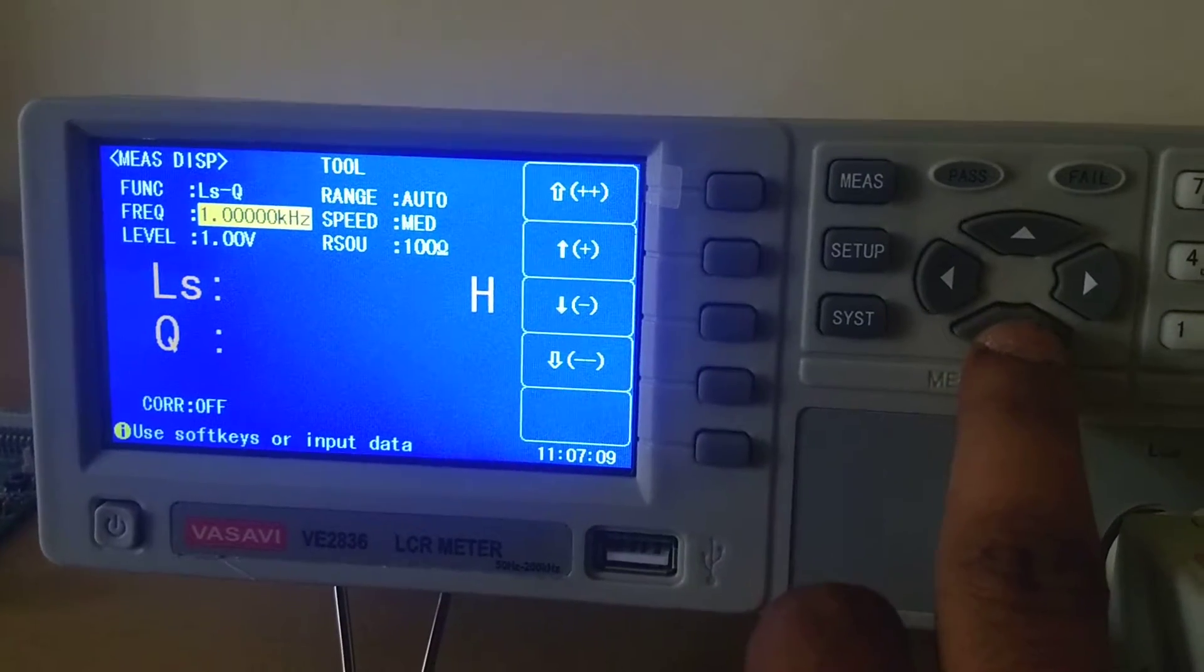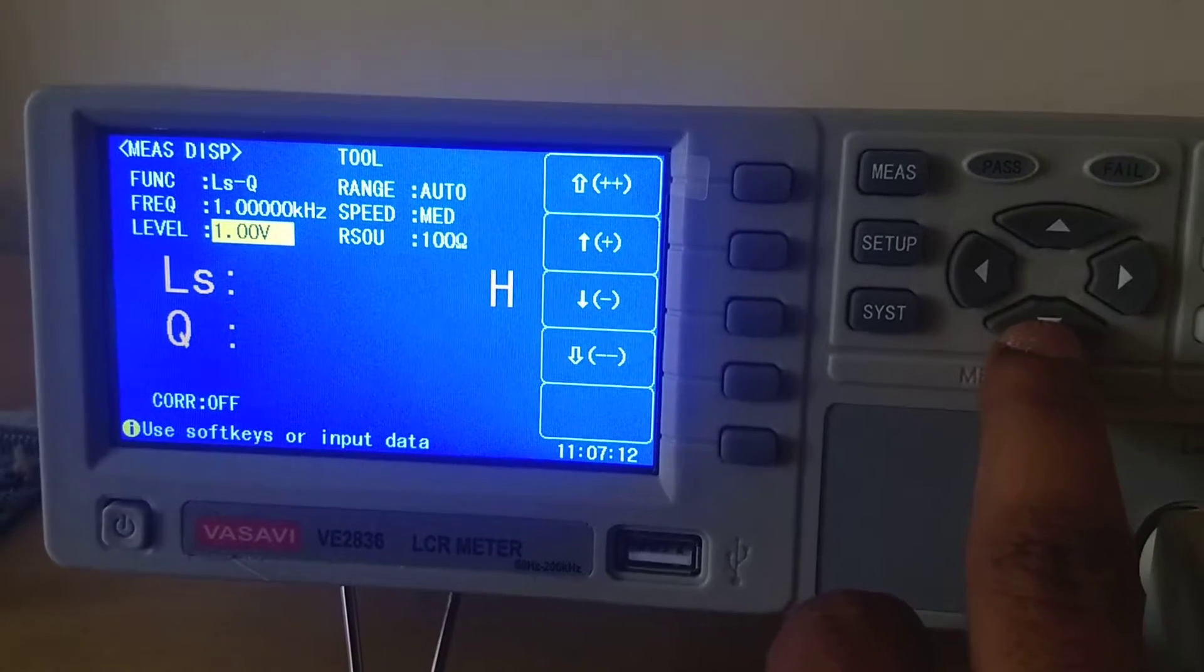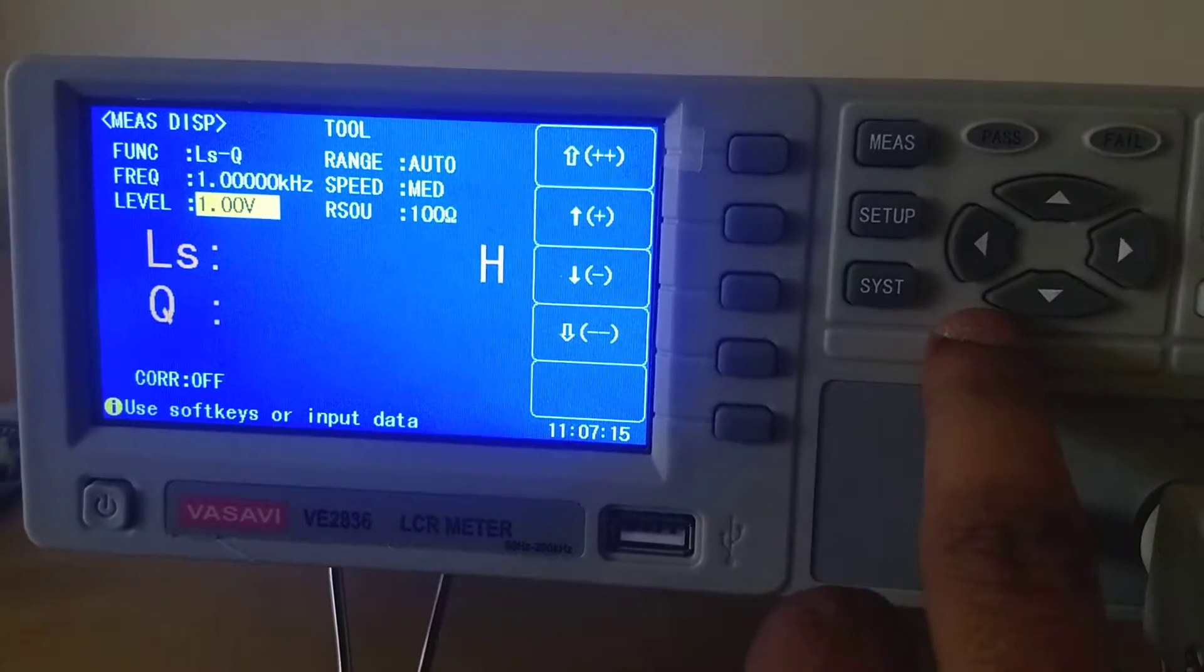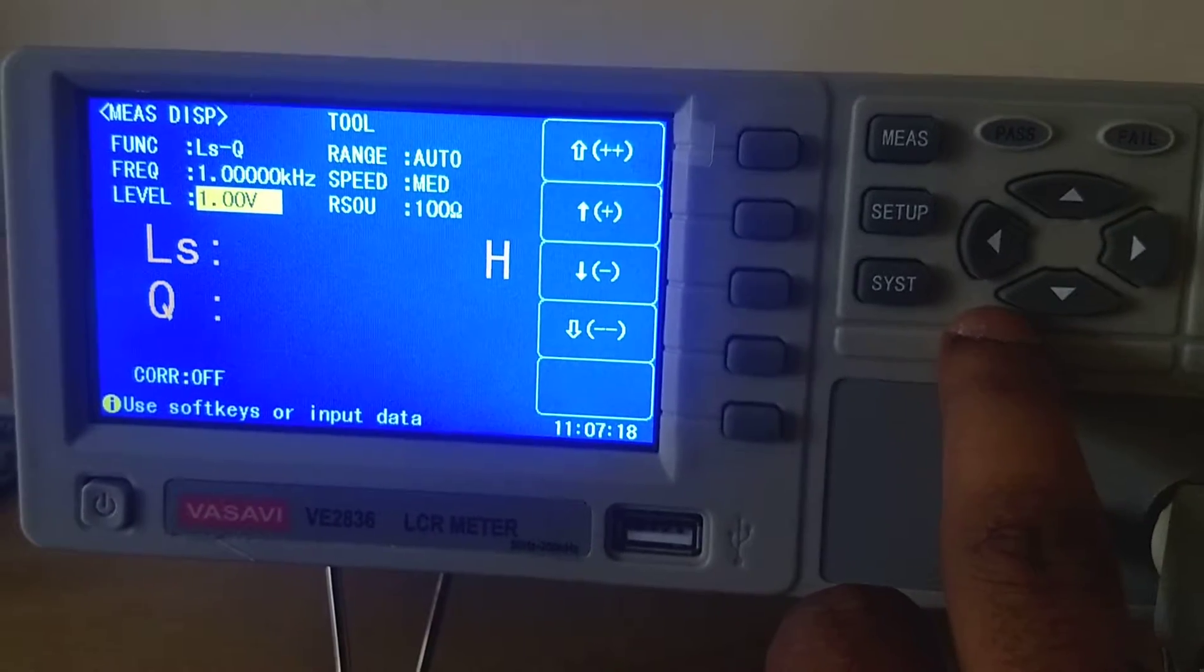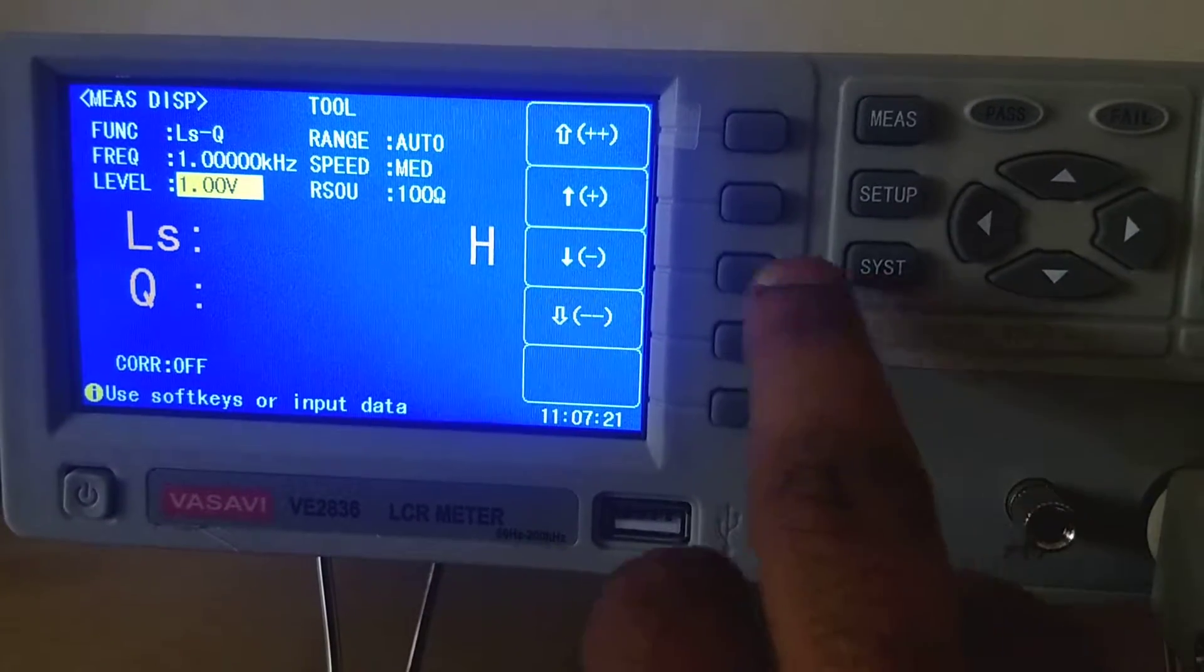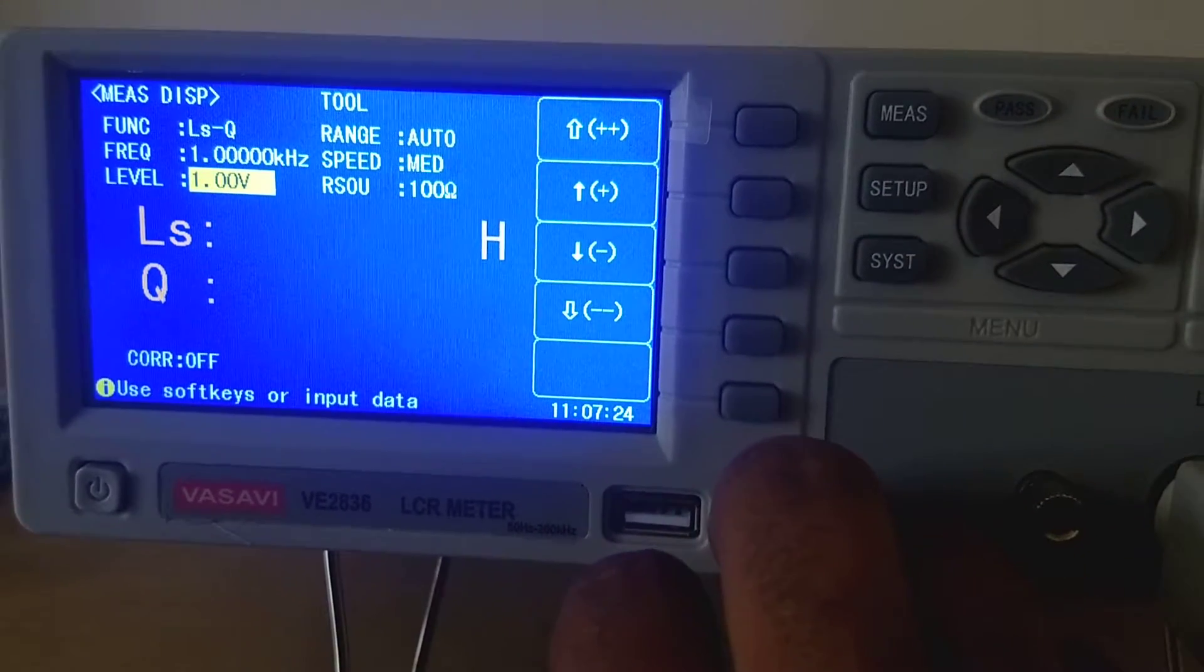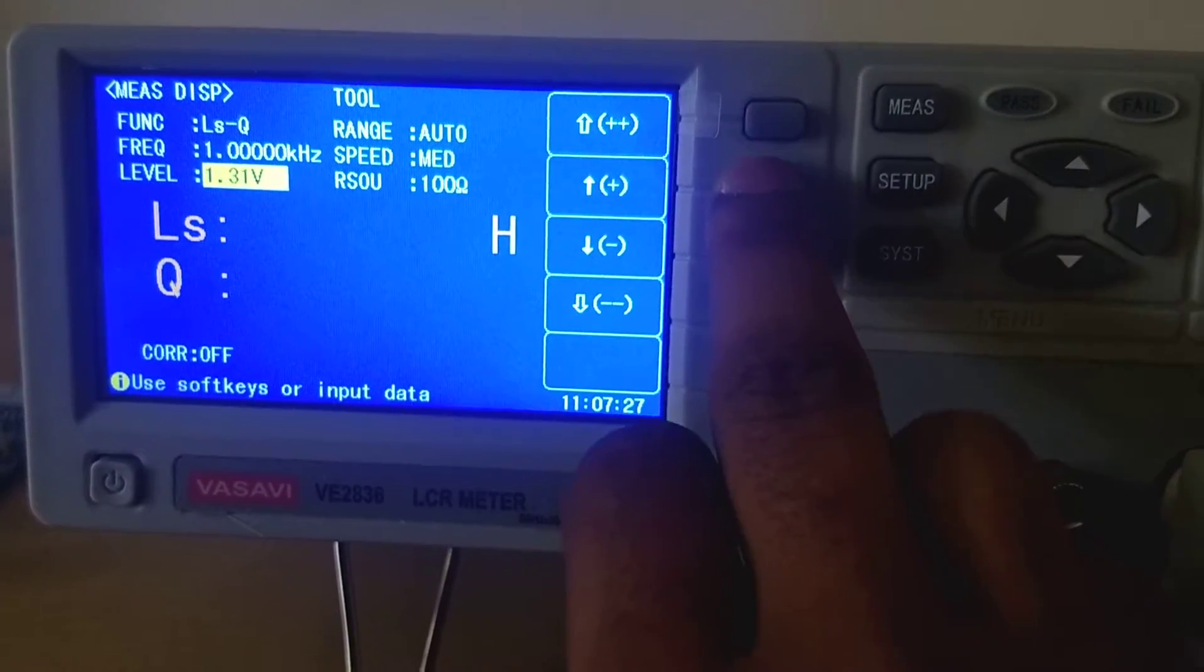Now we will show you how to adjust the voltage. This is the setting of test voltage, which ranges from 50 mV to 2 V. You have increment and fine increment, decrement and fine decrement.